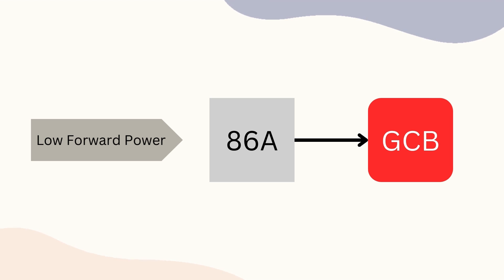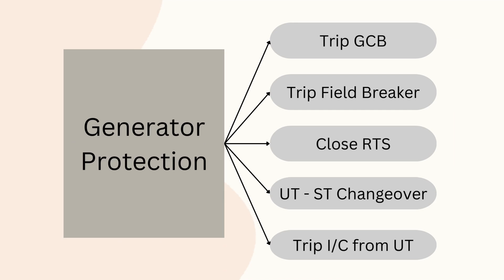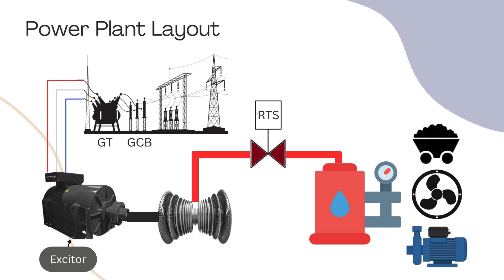These are the basics of Class A, B, and C protection. Now let's delve deeper to understand how these protections work. When these protections operate, the command goes to the GCB, field breaker, RTS, UT/ST changeover, and UT incomer. Understanding this power plant layout is necessary to grasp the effects of different protections.